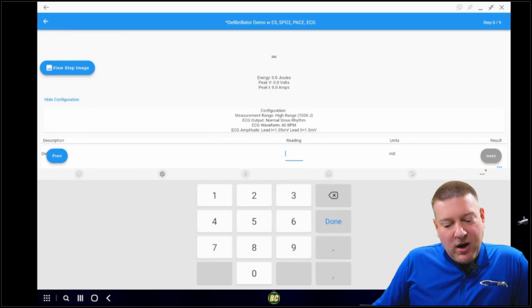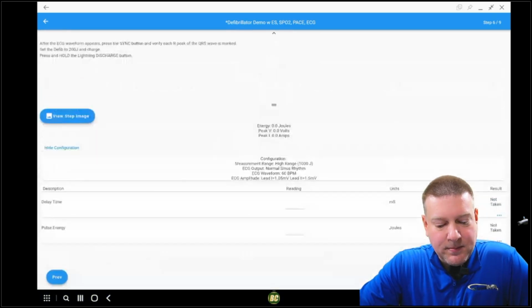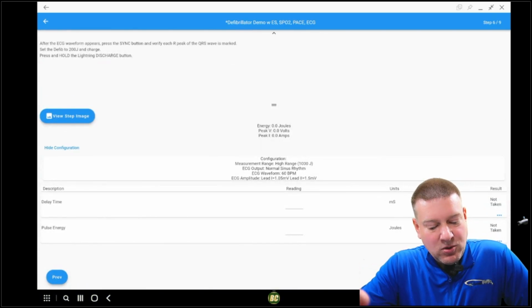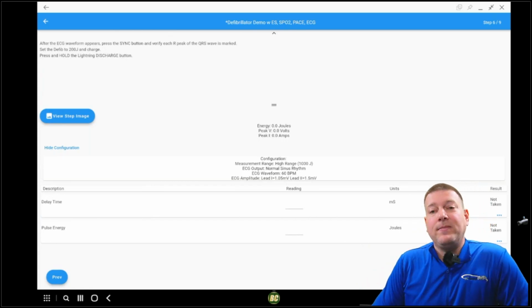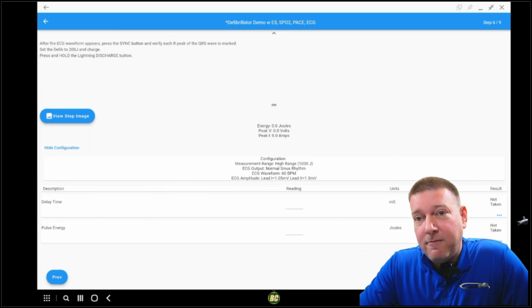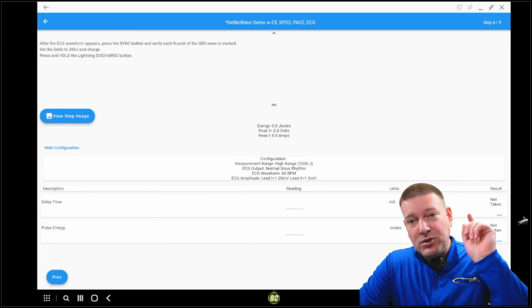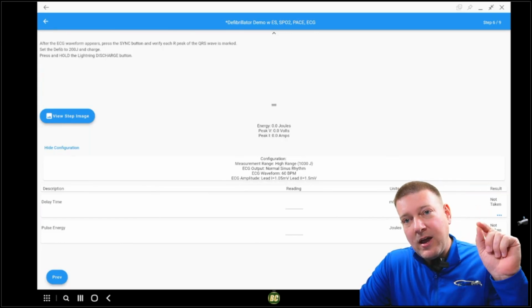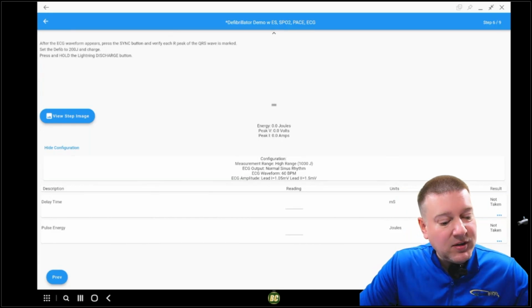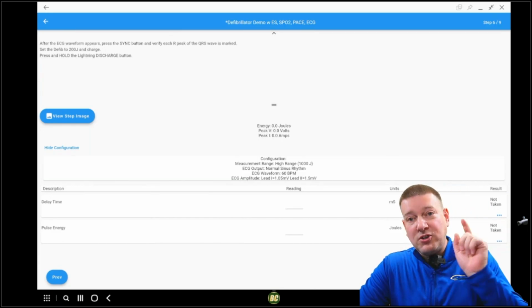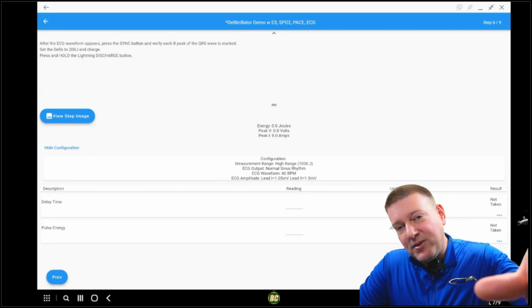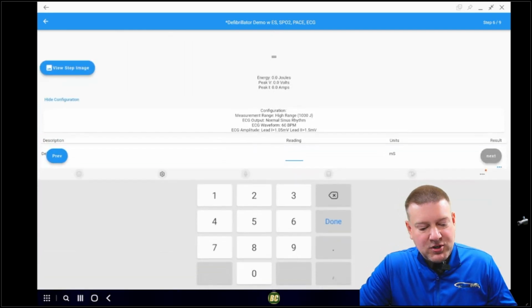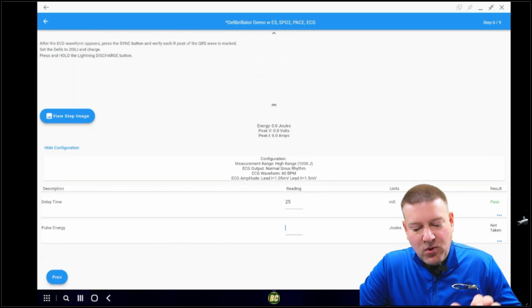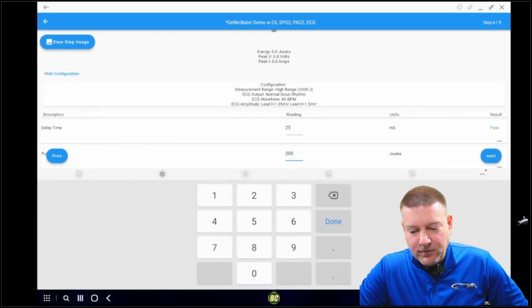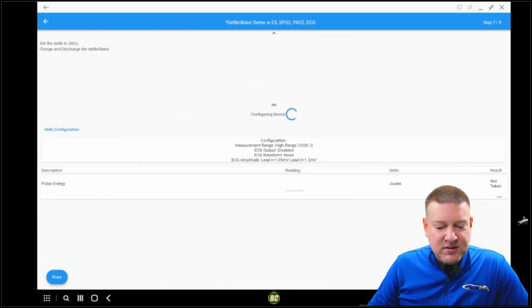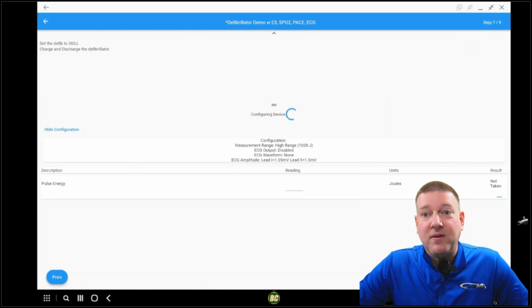So this right here is where we would put it into, the defib's gotta be in manual mode, and then we go ahead and set it up for cardio sync. It's gonna automatically set up your ECG waveform. And from that point, you just have to press the sync button. And then when it marks the pulse, which the instructions tell you right here, then you're going to charge the defib and then press and hold the discharge, and it will automatically capture. And this will automatically populate.